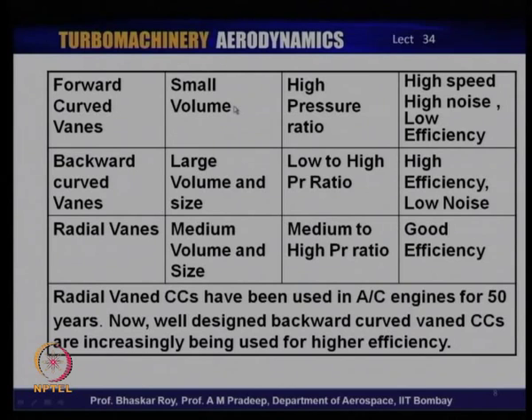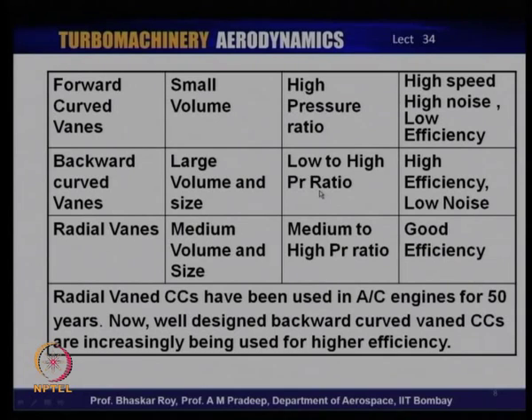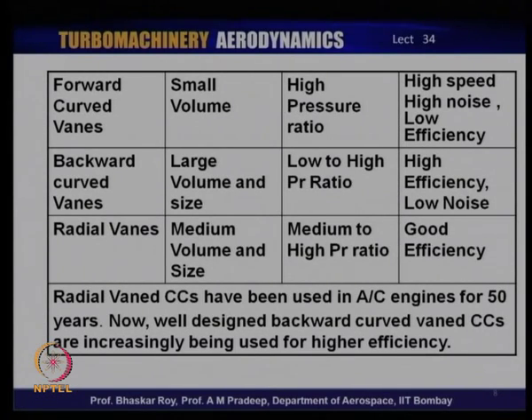Backward-curved vanes, on the other hand, can normally operate with large mass flow and can accommodate higher sizes. It was originally thought to be of low pressure ratio; however, modern designs can actually increase its pressure ratio to substantially high values. They produce high static pressure at the impeller exit and somewhat low exit velocity — and as a result, low noise, with the static diffuser vanes operating at high efficiency. The overall efficiency of the machine is much higher for backward-curved vanes, which is why modern centrifugal compressors are leaning more and more toward backward-curved vanes to produce high-efficiency, low-noise machines.